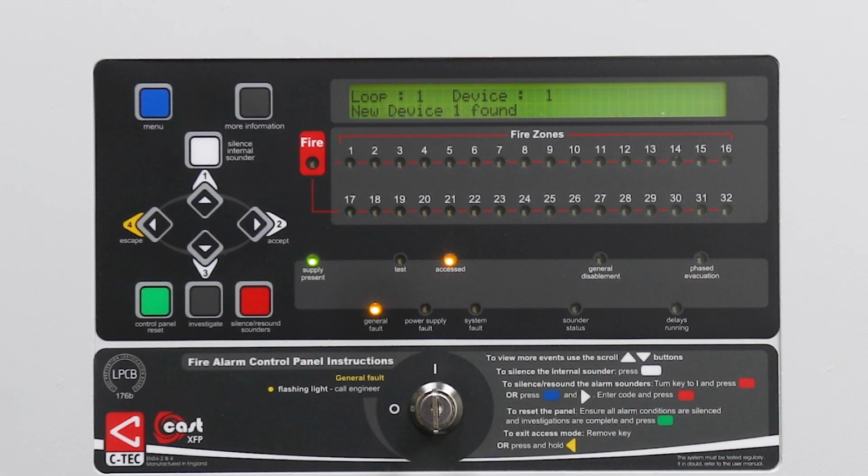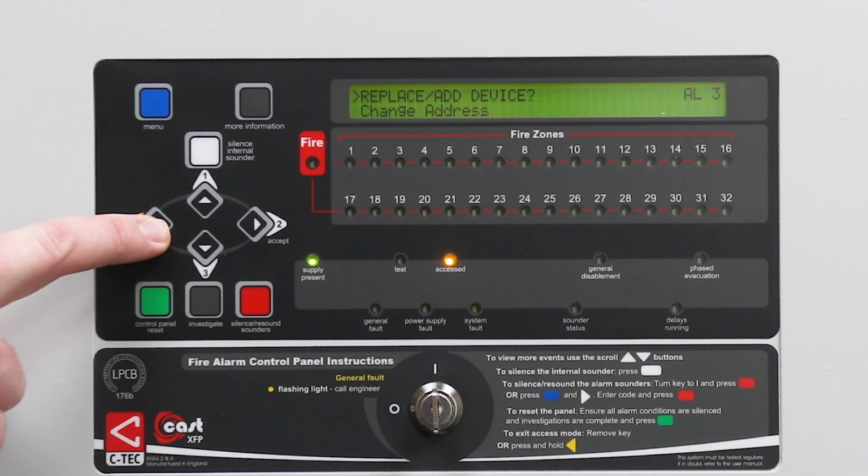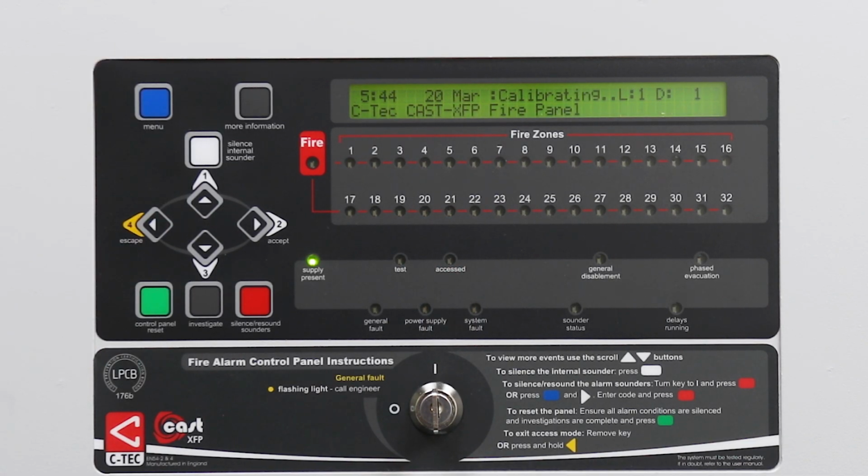Once the device has been successfully replaced, the general fault LED will stop flashing and you will be returned to the replace/add device menu.